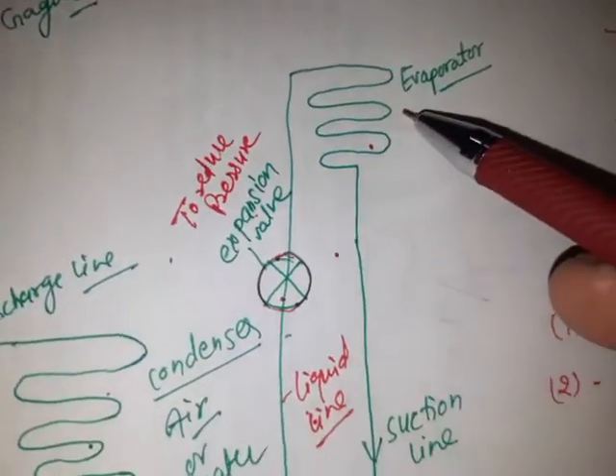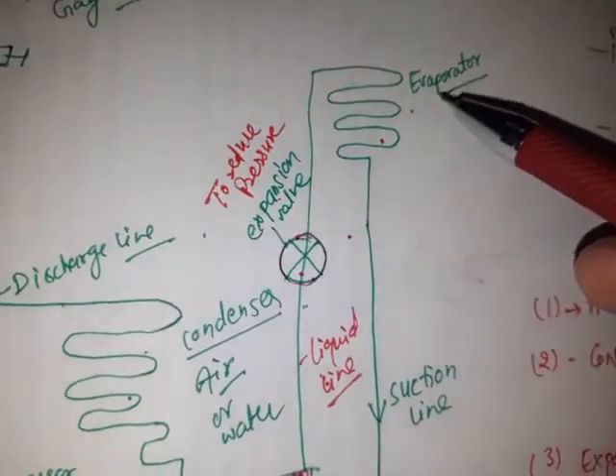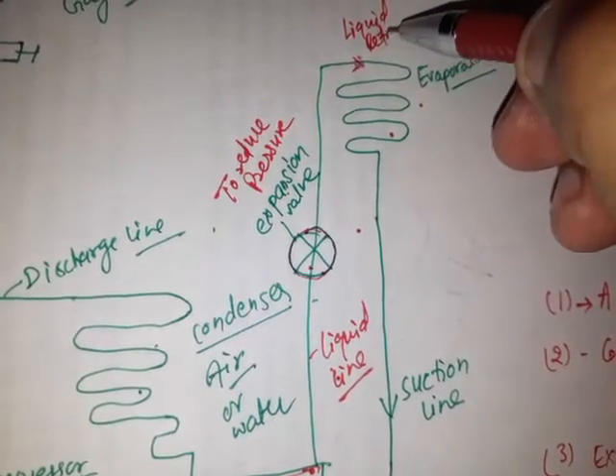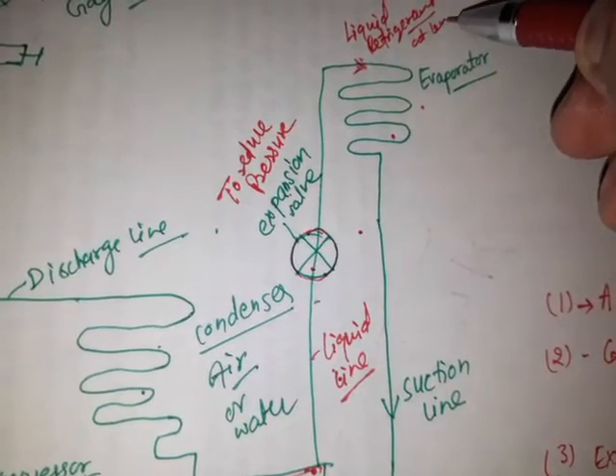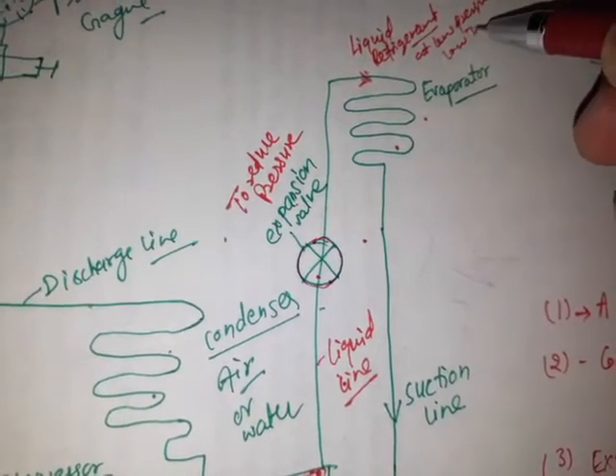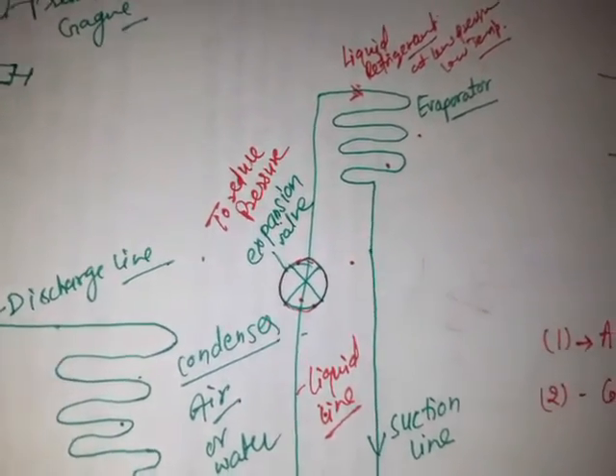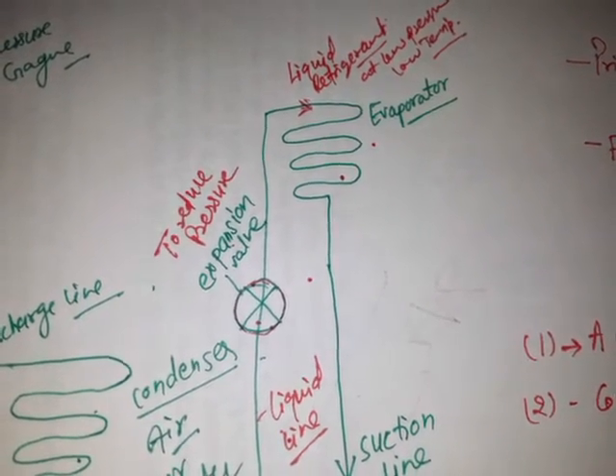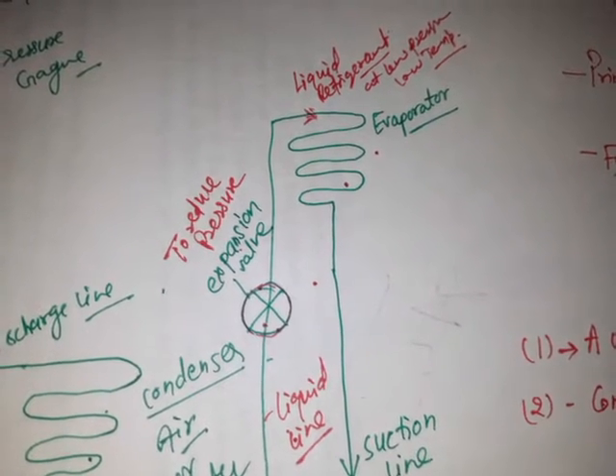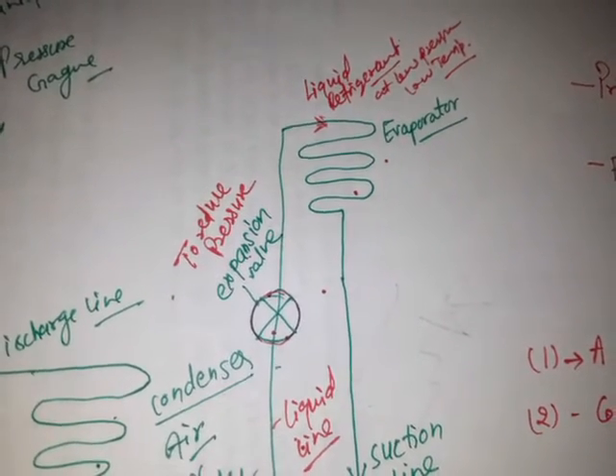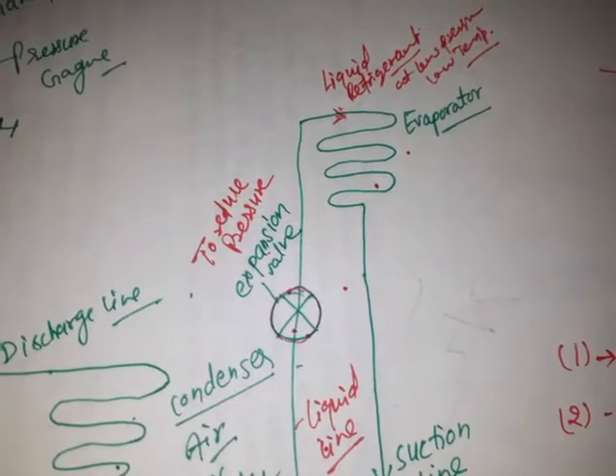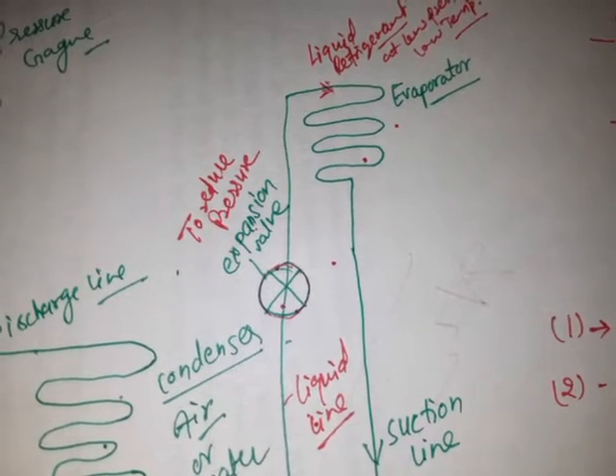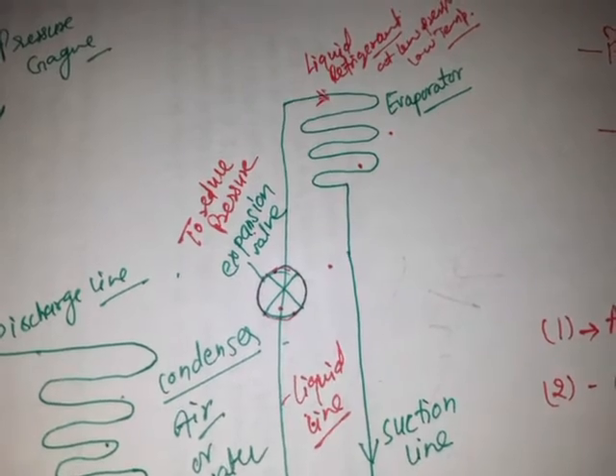The next part is the evaporator. When liquid refrigerant enters at the inlet of the evaporator, it is at low pressure and low temperature. When this low pressure and low temperature liquid refrigerant enters the evaporator, it suddenly expands and takes the latent heat from the evaporator, because the temperature of the evaporator is lower than the surrounding temperature, so it absorbs heat from the surrounding or refrigerated space, and evaporation takes place producing cooling.